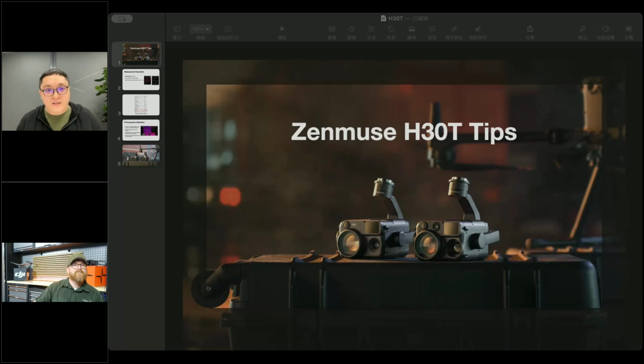So the second thing is we now allow you to do the IR temperature calibration. To do this, you need to prepare 3 black bodies from low, medium, and high temperature. For example, 20, 50, and 150, something like that. The black bodies are something that have a stable temperature. If you don't know what a black body is, maybe this feature is not designed for you.